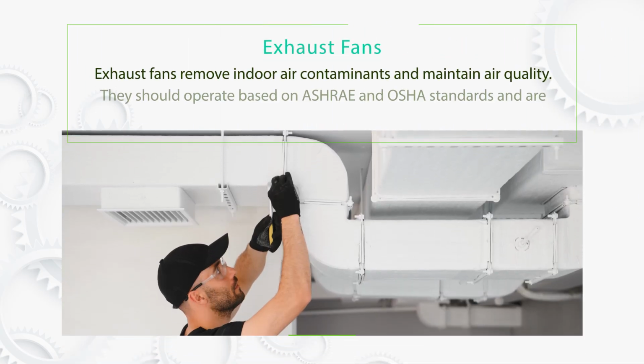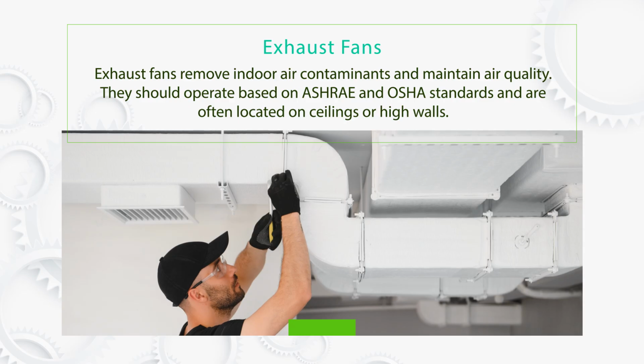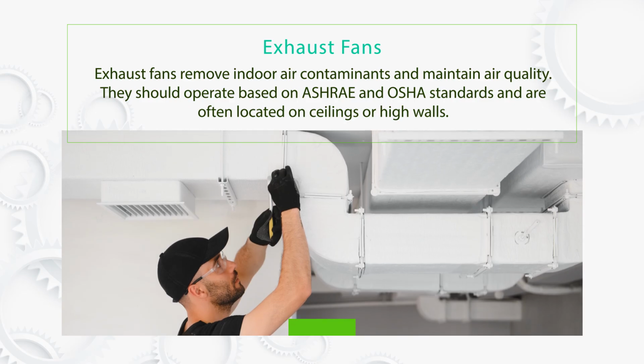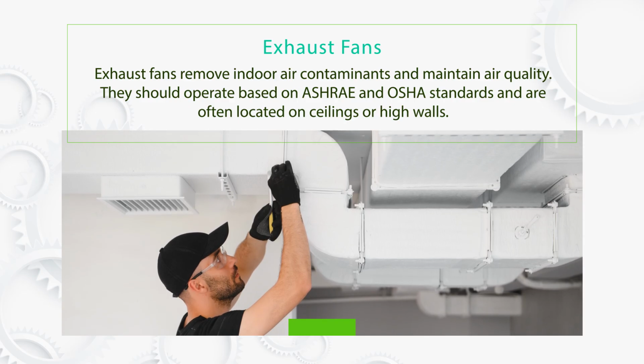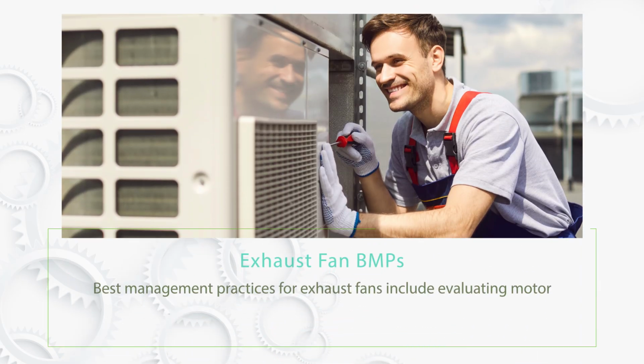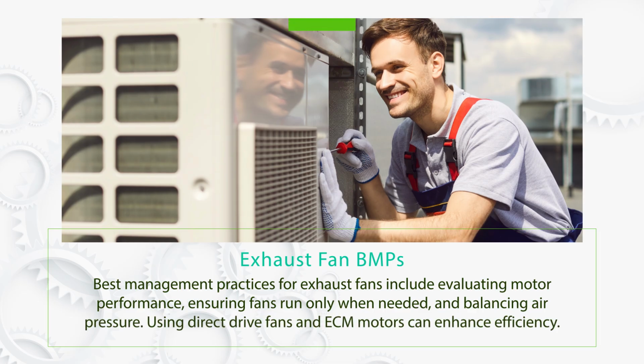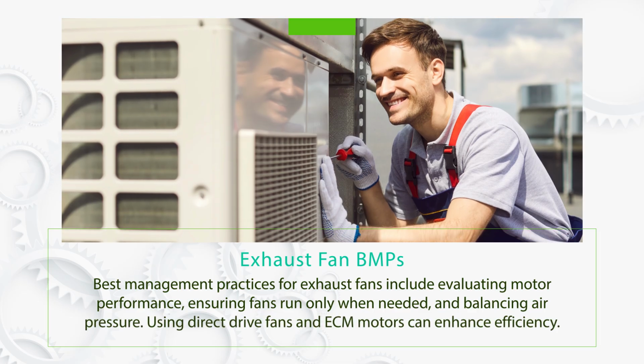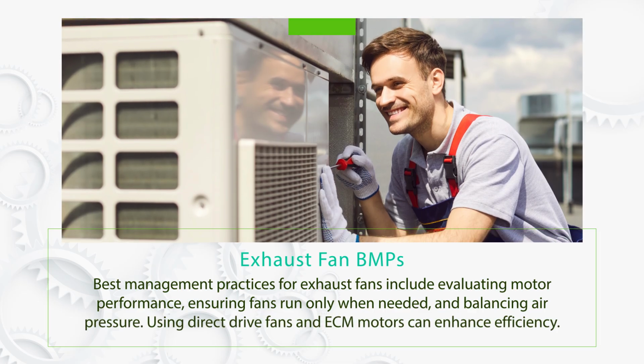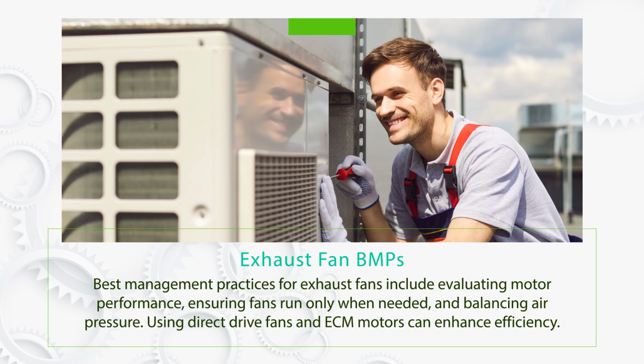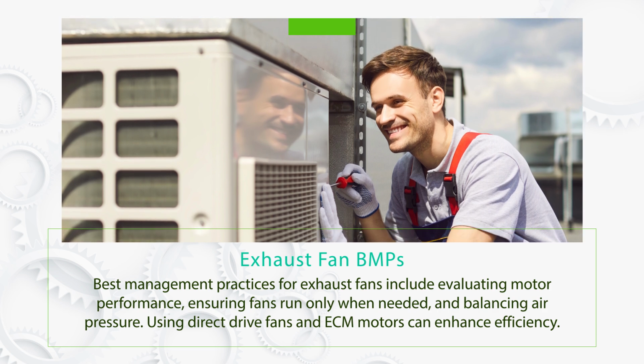Exhaust fans remove indoor air contaminants and maintain air quality. They should operate based on ASHRAE and OSHA standards and are often located on ceilings or high walls. Best management practices for exhaust fans include evaluating motor performance, ensuring fans run only when needed, and balancing air pressure. Using direct drive fans and ECM motors can enhance efficiency.